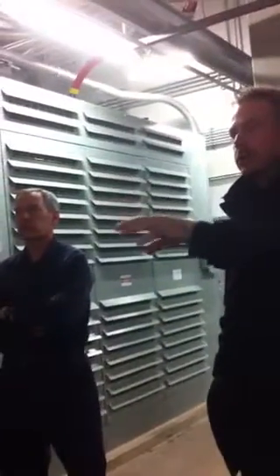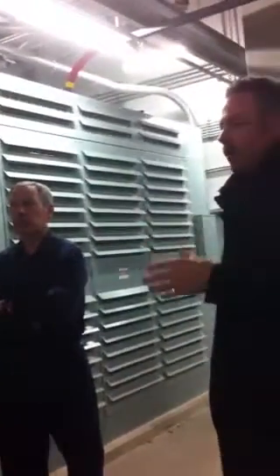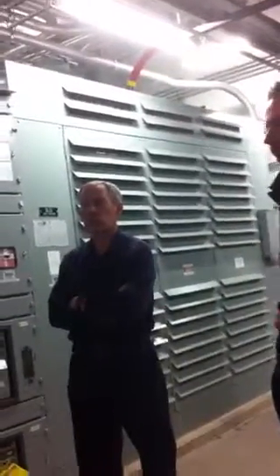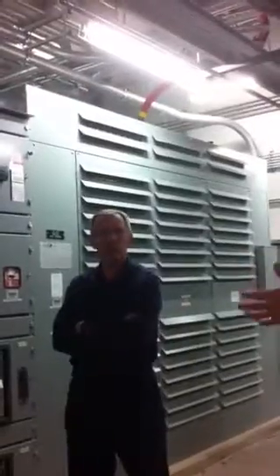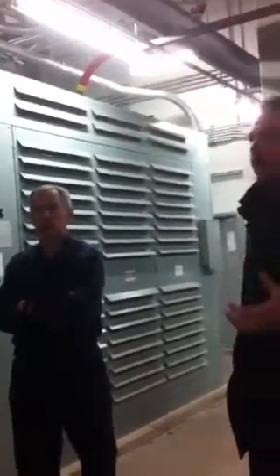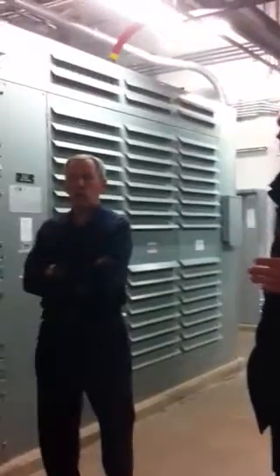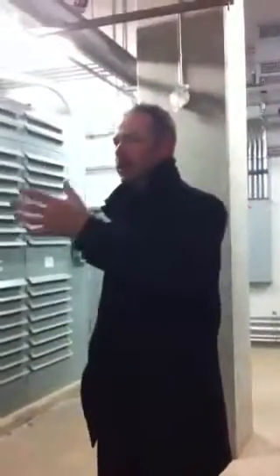These are 12, 16, 18-week delivery to get a transformer like this to be replaced. So more and more we're seeing in the new buildings of the university this type of redundant system put in, where you've got essentially a double-sized system where you minimize your downtime. Now I don't know the last time, Raymond can attest, of when we've actually had a facility go down for a long duration of time because of a power outage. Ideally, if you lost a transformer in this room, your occupants would probably never really know it.